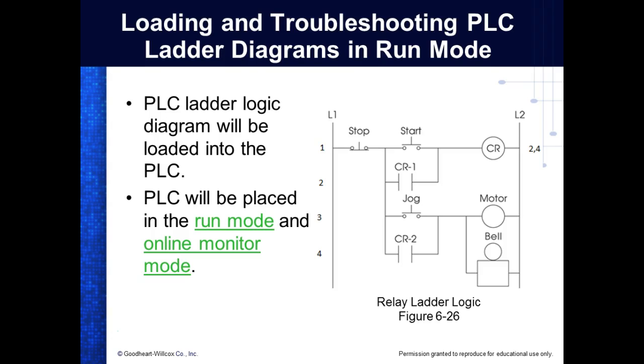So what are these over here? Those would be line numbers. They're not rung numbers. In motor controls, we don't deal with rungs. In motor controls, we use lines. We don't number the rungs, we number the lines. In PLCs, we number the rungs. Right? You understand? We still call them a rung, but any line that runs horizontal, it's a number. These are cross-reference numbers, and what do they show you? Which line contains the contacts, right? Okay. Everybody okay? Yes or no?